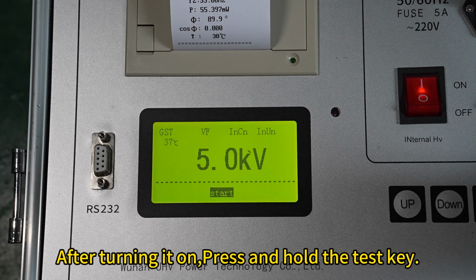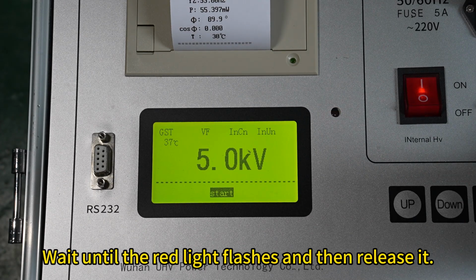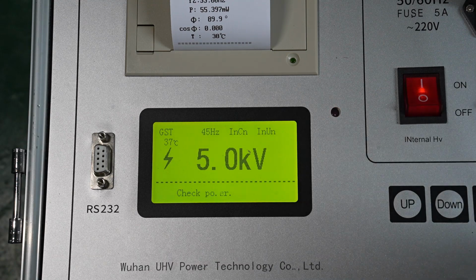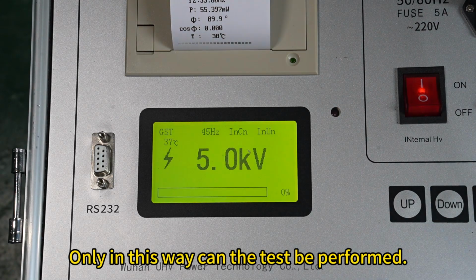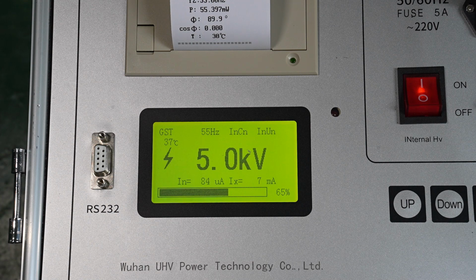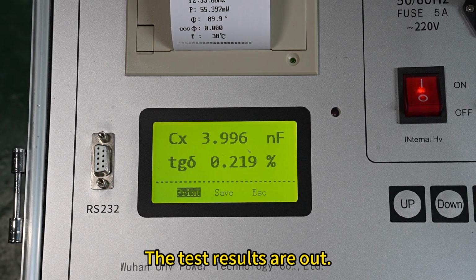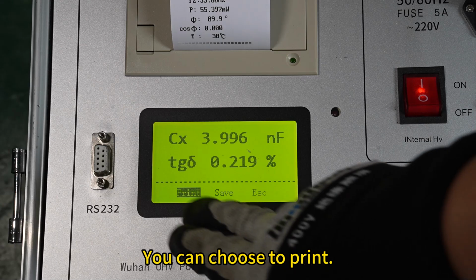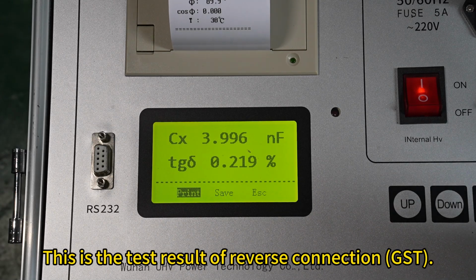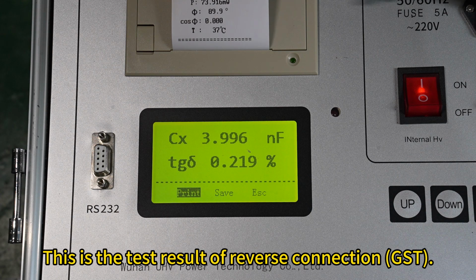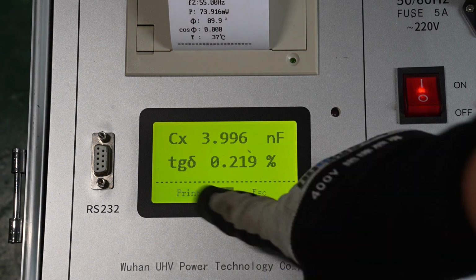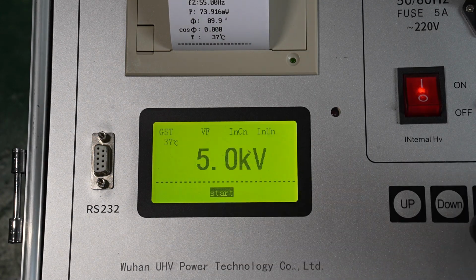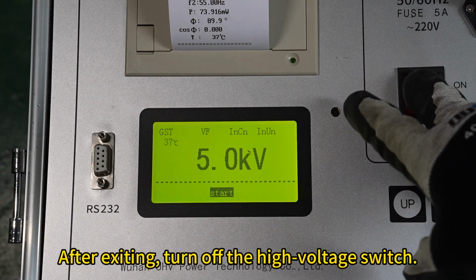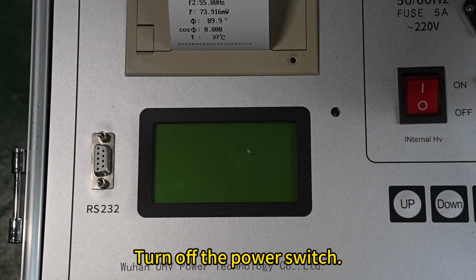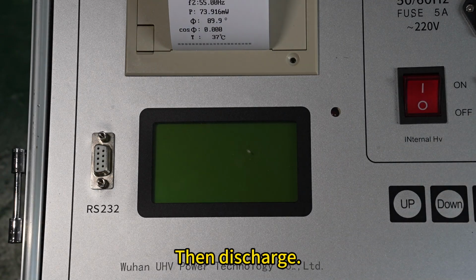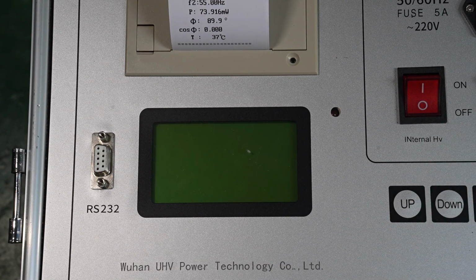After turning it on, press and hold the test key. Wait until the red light flashes, and then release it. Only in this way can the test be performed. The test results are out. You can choose to print. Click OK. This is the test result of reverse connection, GST. You can also save it. We will not save it here. Click to exit directly. After exiting, turn off the high voltage switch. Turn off the power switch. Then discharge. Remove the wires. The test is completed.